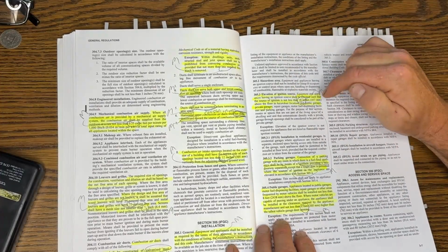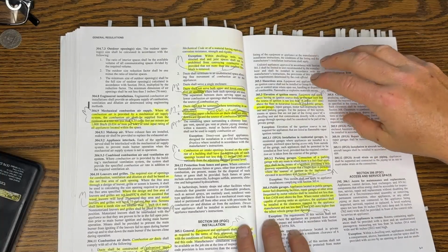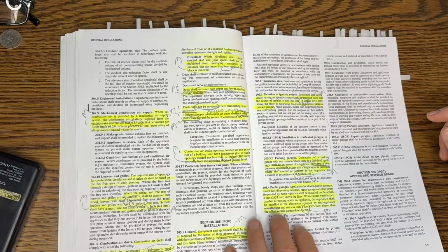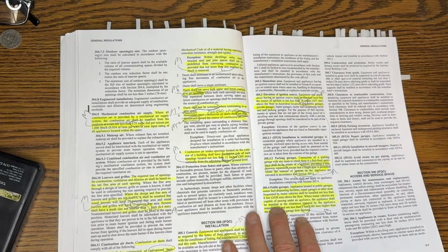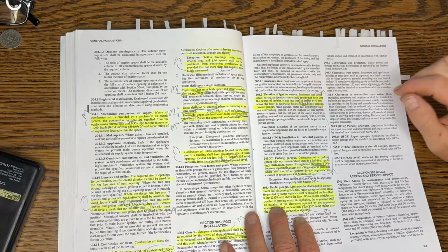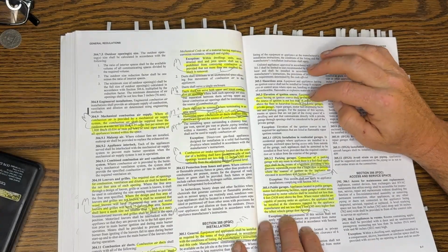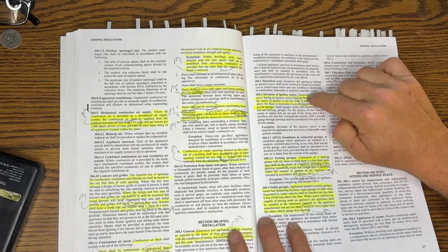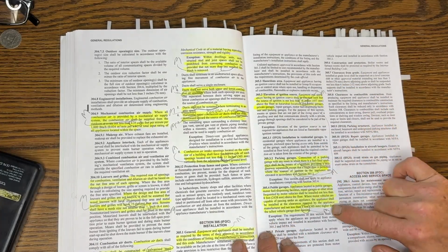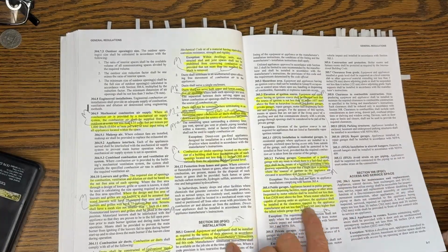Elevation of ignition source, 18 inches. This is because if you have a pilot light, you don't want heavier than air combustible gases to accumulate and ignite. You're not too worried about CH4, which is methane, because it floats and dissipates, but propane, C3H8, is a lot heavier than air, 44. It's about 1.5 times heavier than air, so it tends to accumulate. So that's why you have this prohibition. So yeah, just have some protections you need here and there.